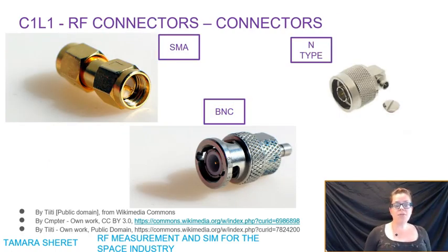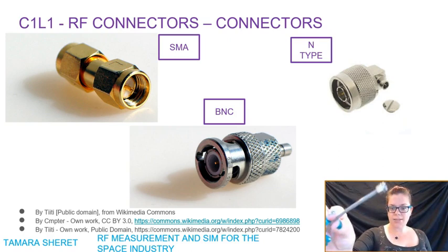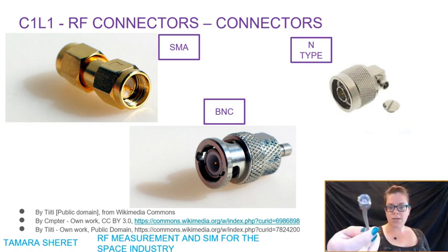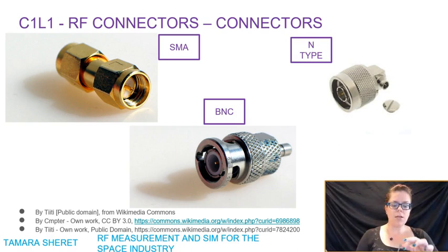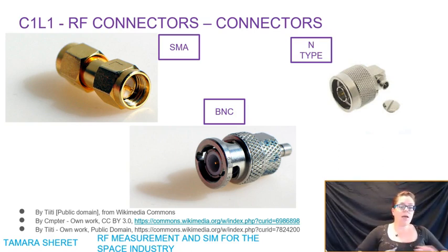The connectors you use most commonly are an SMA connector. Whatever you buy will come with a dust shield, which you need to keep on to protect it from dust. Take the shield off, and this is an SMA connector. You can see the pin in the centre is your coaxial middle centre. You've got the shielding around the outside, and you just screw that into place. N-type, BNC, exactly the same idea, just slightly bigger, tend to be used for different frequencies and different powers. So what connector you use doesn't matter as long as it's suitable for your power and your frequency requirements.